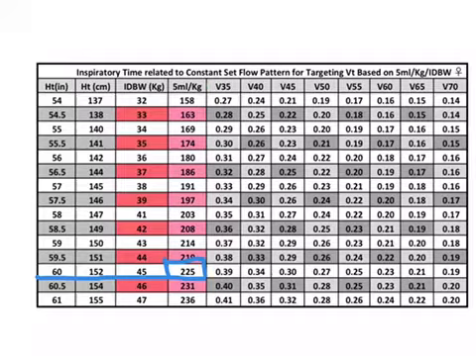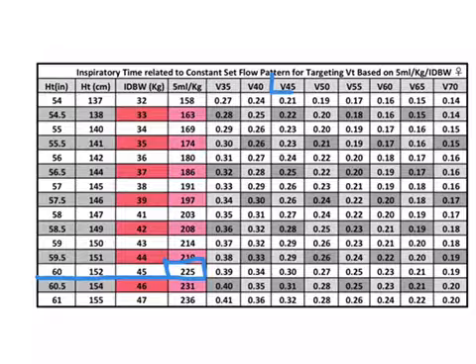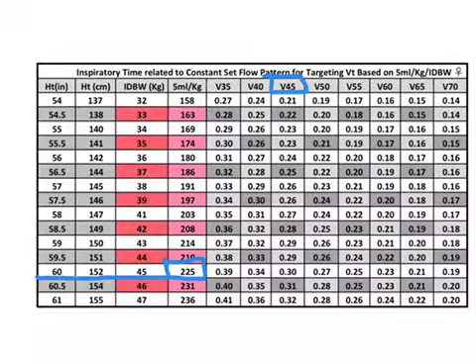And let's say the ventilator is set up, instead of setting an inspiratory time, I set a flow rate and we're setting the flow rate up for 45 liters. And as you can see that my inspiratory time now gives me 0.3.